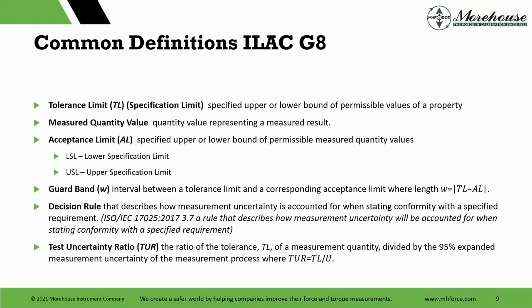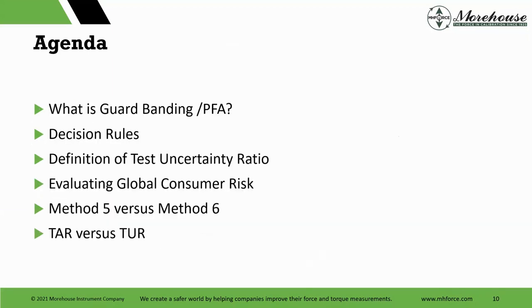So this is important because of how measurement uncertainty will be accounted for. We're going to discuss this in detail, and then test uncertainty ratio, the ratio of tolerance of the measurement quantity divided by 95% expanded measurement uncertainty of the measurement process. We're going to go over all these. The agenda, things we're going to discuss: method 5 versus method 6. I might veer off and talk a little bit about other things.